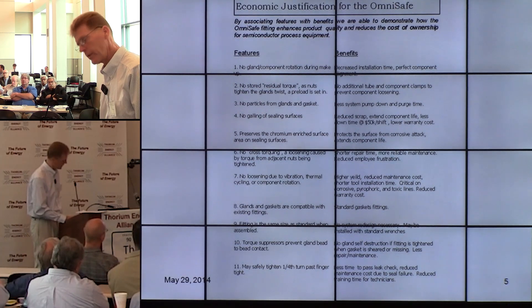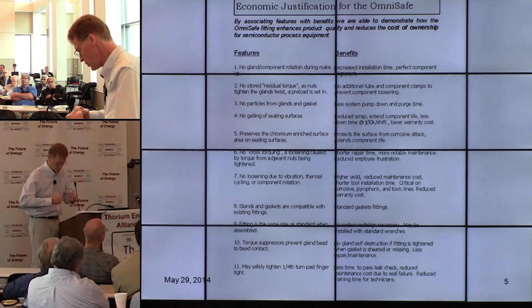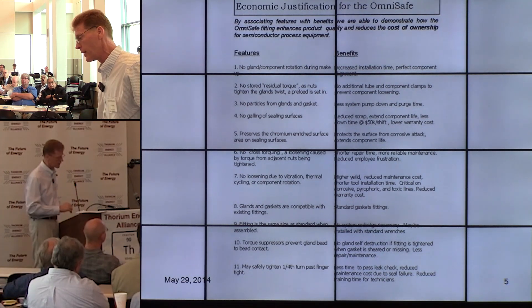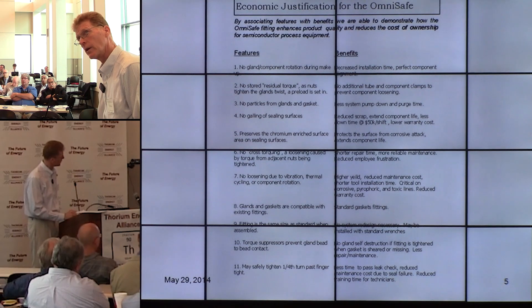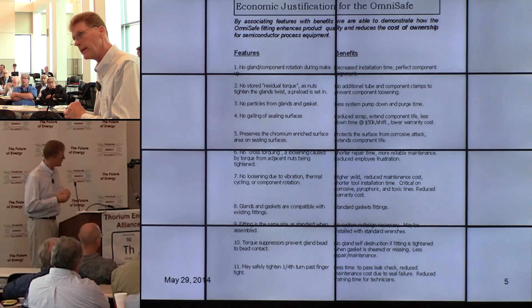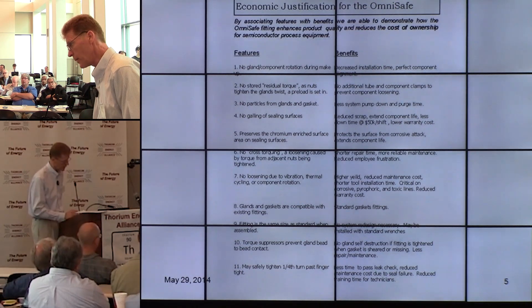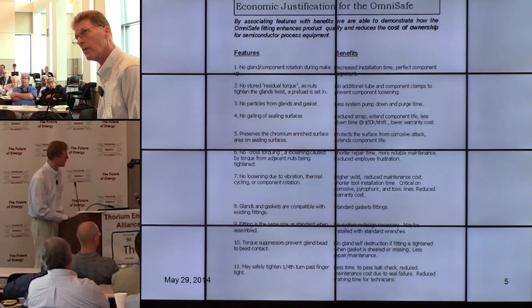There's another problem with the standard fitting: if the gasket is missing, the two toroids of the two glands crush into each other, destroy each other, and there's no way to repair it — it has to be thrown away. With our fitting, the torque suppressors stop bead-to-bead contact and destruction. It fails safe — it doesn't pass leak check, you take it apart, put your gasket in, and continue without any problems.